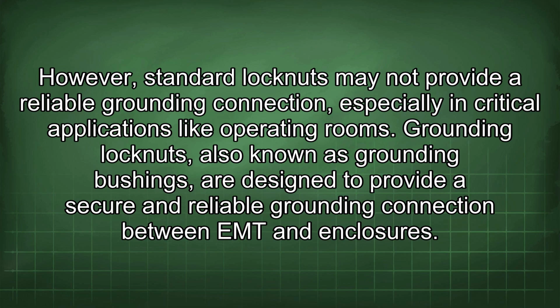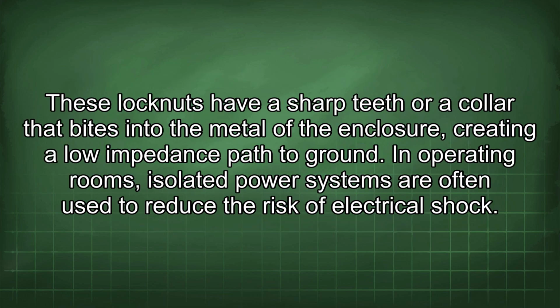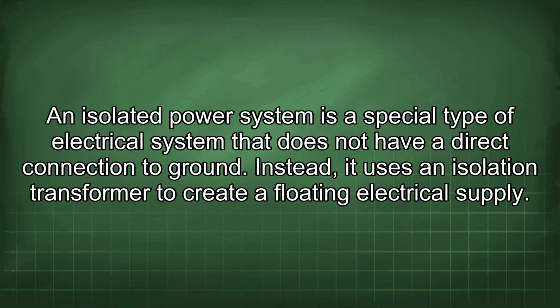Grounding locknuts, also known as grounding bushings, are designed to provide a secure and reliable grounding connection between EMT and enclosures. These locknuts have sharp teeth or a collar that bites into the metal of the enclosure, creating a low-impedance path to ground. In operating rooms, isolated power systems are often used to reduce the risk of electrical shock. An isolated power system is a special type of electrical system that does not have a direct connection to ground. Instead, it uses an isolation transformer to create a floating electrical supply.